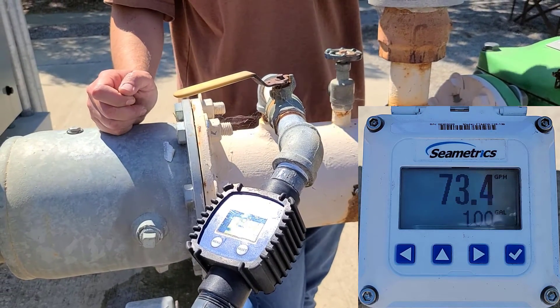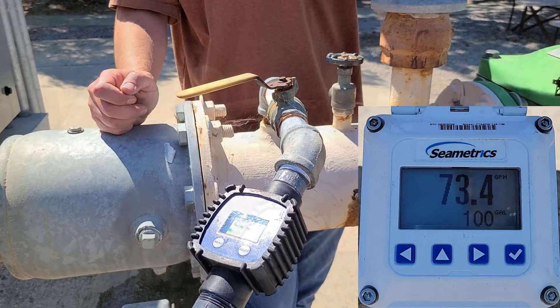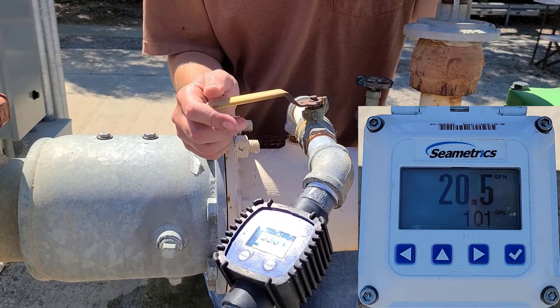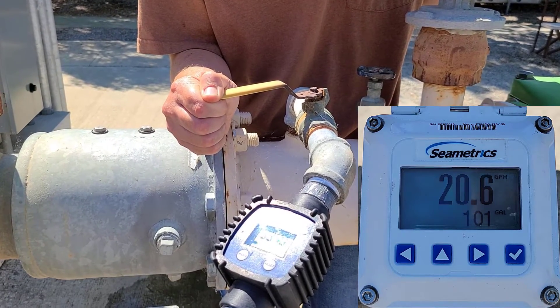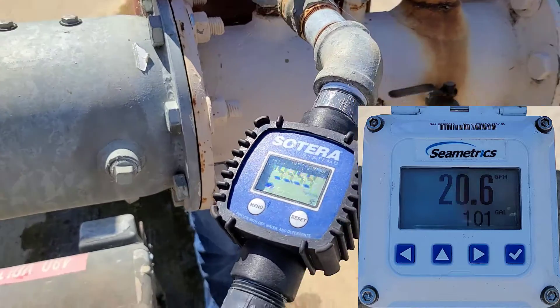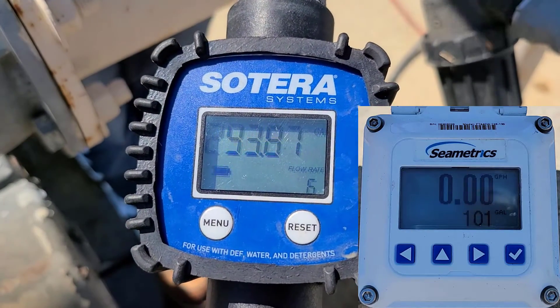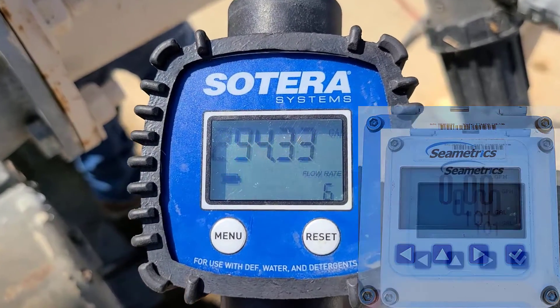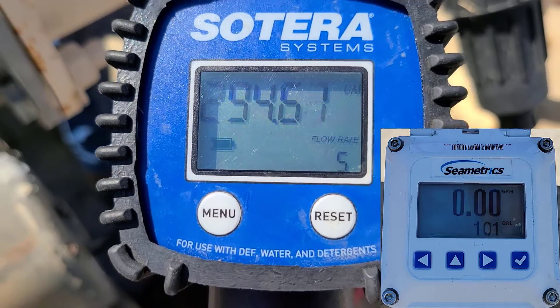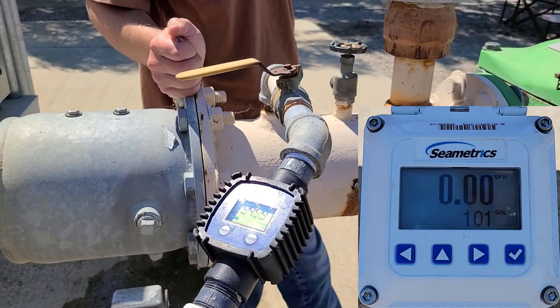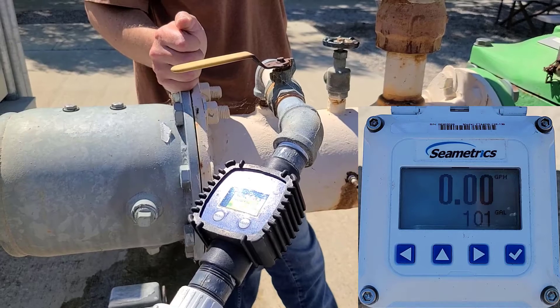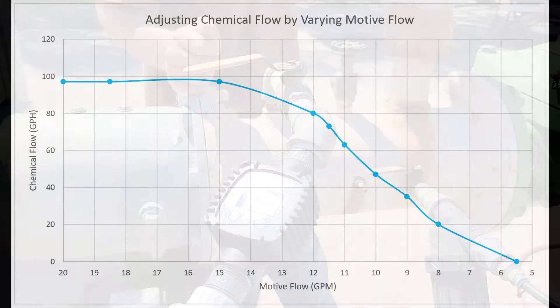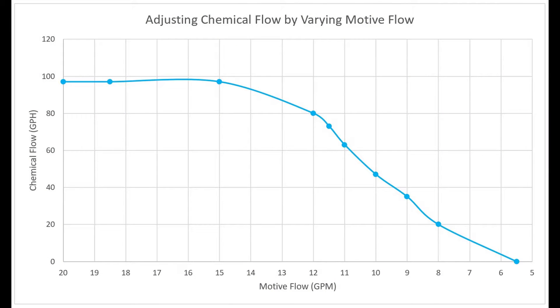You can see it took us a few attempts to get to 75. If we try to go even lower — say 5 gallons per hour — you'll notice it becomes extremely difficult to hold a very low flow. You can see it drop to zero while the motive flow rate is still 6 gallons per minute. You have to have enough flow through the venturi to maintain vacuum and suck the chemical in, so this is difficult to do.